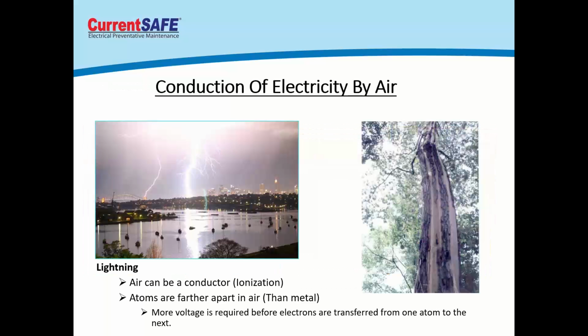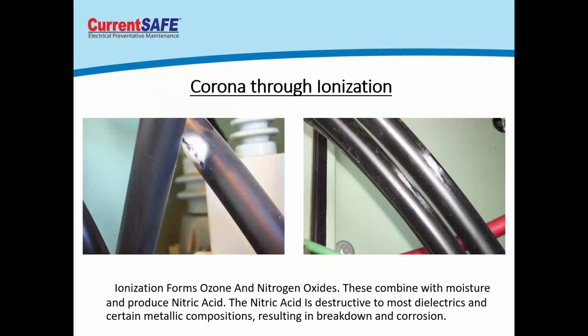So I've got some other slides here. I'm not going to go through talking about corona and what it is really, but you can see some nitrates build up on these cables. This is another anomaly that we detected on a 5 kV motor starter in a helium compressor building. And you can see that.